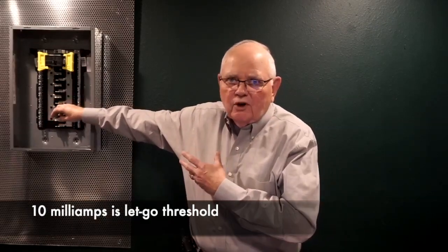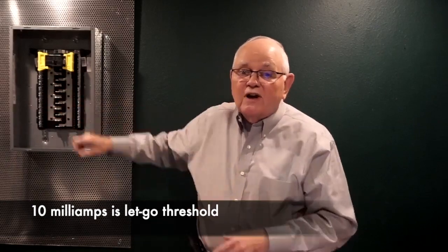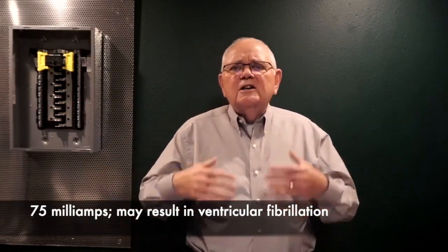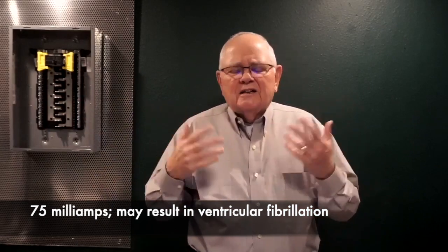Now, if you look at the numbers, how much current does it take to shock us? One of the concepts is if I grab a hold of something at about 10 thousandths of an amp of current flow, that's 10 milliamps of current flow. That's enough current flow to cause my muscles to contract to where I can't let go. And of course, the result of that, if I can't let go, could be a fatality, because by the time I get up to about 75 milliamps, my heart can go into ventricular fibrillation, where it beats erratically, sort of like a pump that cavitates, right? The pump that cavitates can't get proper flow through it. And if my heart is beating erratically, it can no longer deliver that blood flow that it needs to.